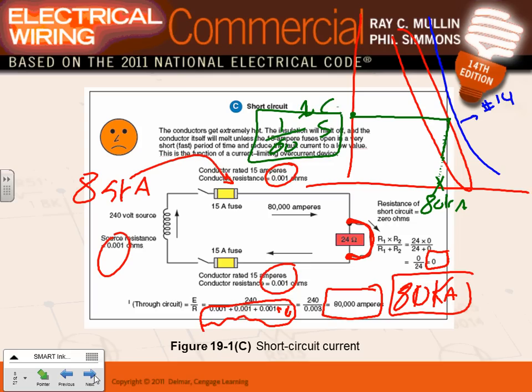1/60 of a second. Anybody can imagine or see 1/60 of a second? Can you feel 1/60 of a second? So fast. You have a short circuit, your fuse is going to open so fast. Versus, remember the first condition, guys, when we had 20 amps, we went all the way up to here, and we opened at, did they say 1 hour last time? Yeah, 1 hour. So if you overloaded, it took 1 hour to open on an overload, depending on how high the overload, right? Versus short circuit, 1/60 of a second.